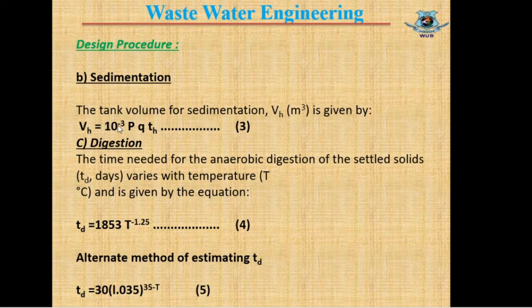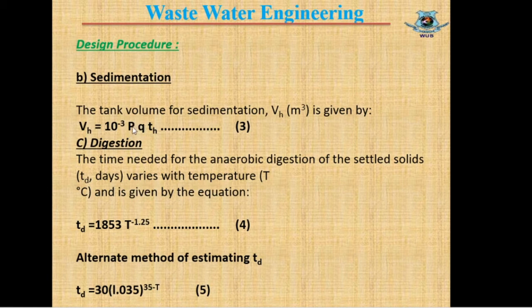The volume of the sedimentation zone VH is calculated as: VH = P × Q × TH × 10⁻³, where P is population, Q is wastewater flow in liters per person per day, and TH is the sedimentation time in days. The factor 10⁻³ converts liters to cubic meters, giving VH in m³.